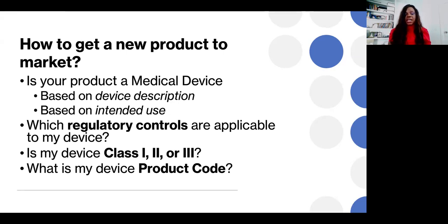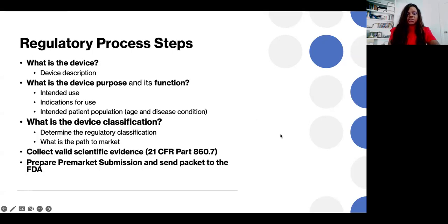And then we have to get into the regulatory controls which the FDA put in place, and we have to figure out if those controls are applicable for our device. We have to ask ourselves if our device is a class 1, 2, or 3, and that's the way the FDA classifies devices into 3 classes. And then we will get a unique product code that would be specific for our device and our device type. Next slide, please. So this is really the regulatory process steps that we would normally go through.